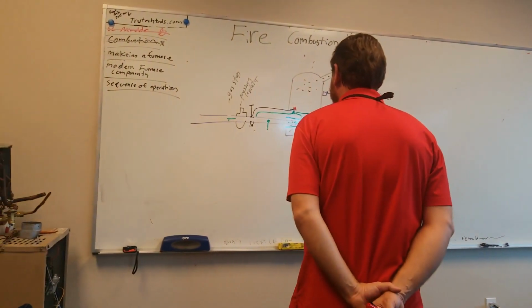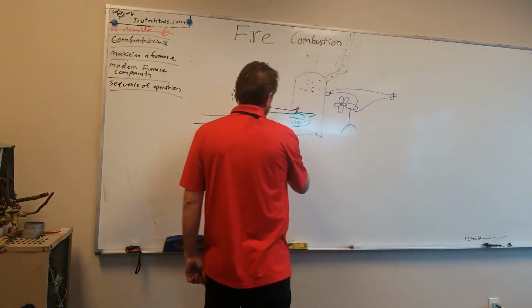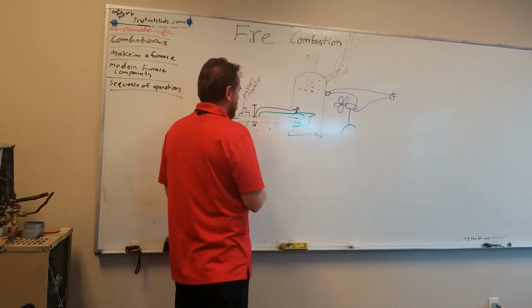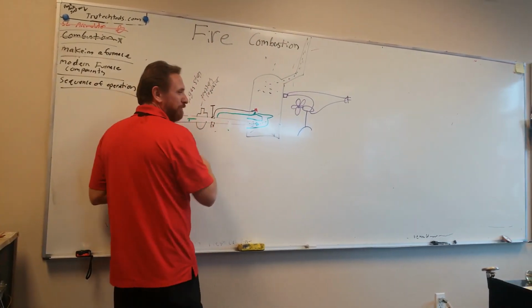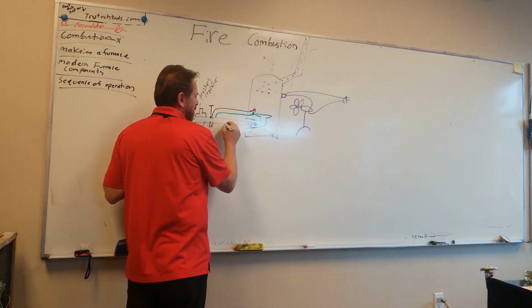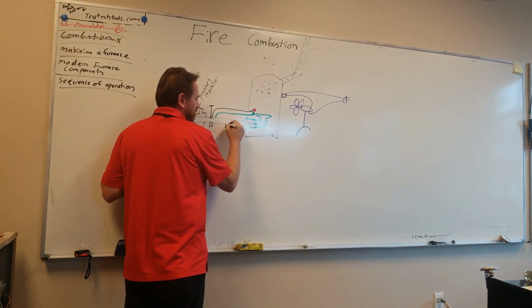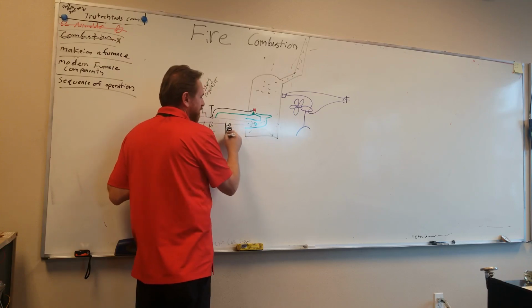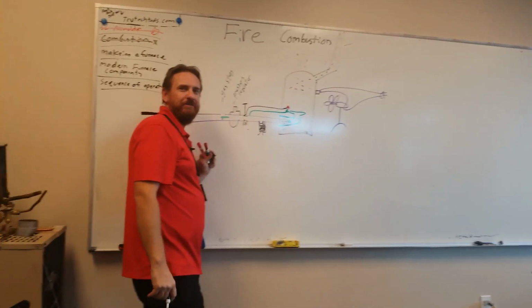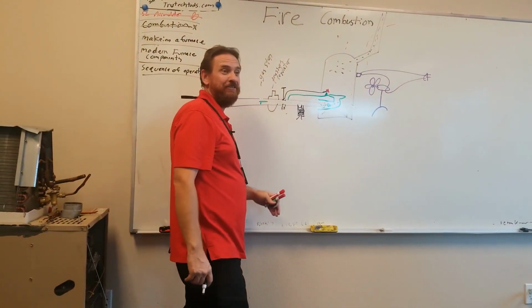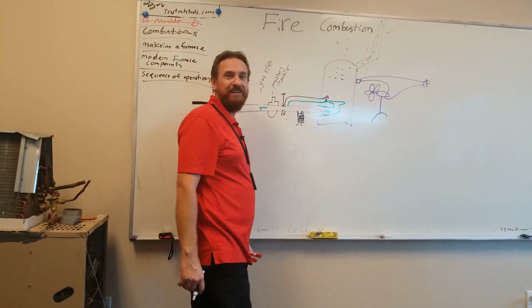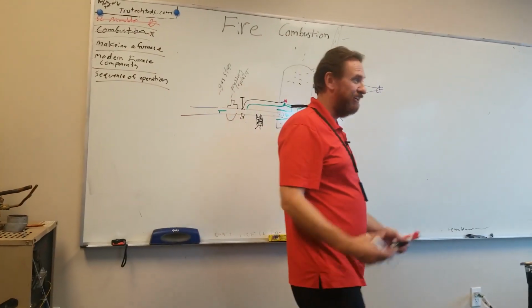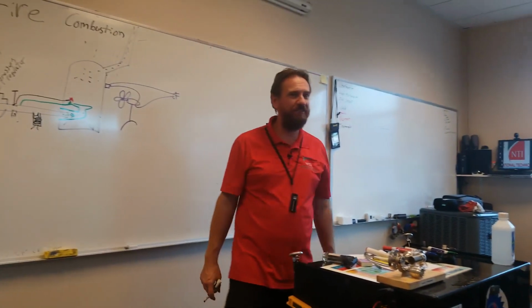Okay, well, let's see if we can come up with a way to automate this more. So, what if I replace this valve with another solenoid valve, kind of like this one? So I put a solenoid here. So now that's an electrically operated valve. I create an electromagnet and it opens the valve. I kill the electromagnet and the valve closes. How does that sound? Sound good? A solenoid valve.